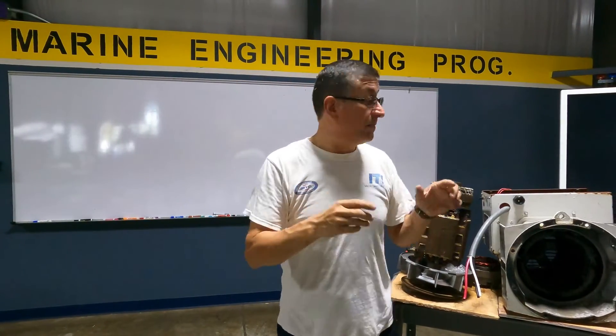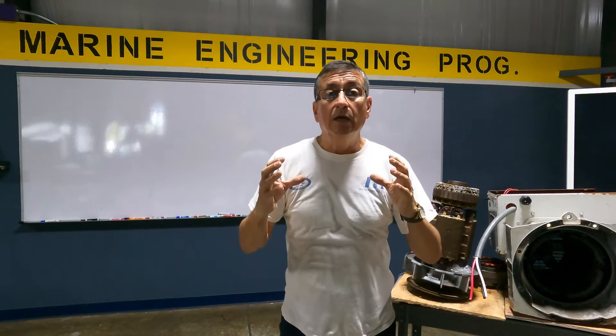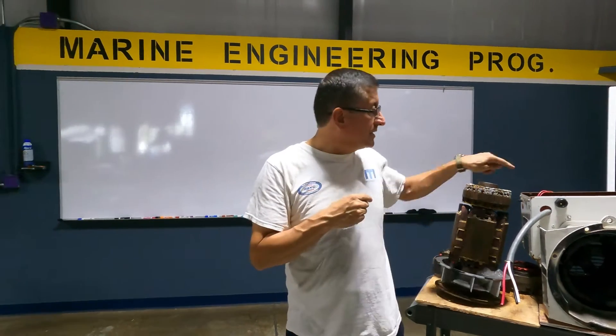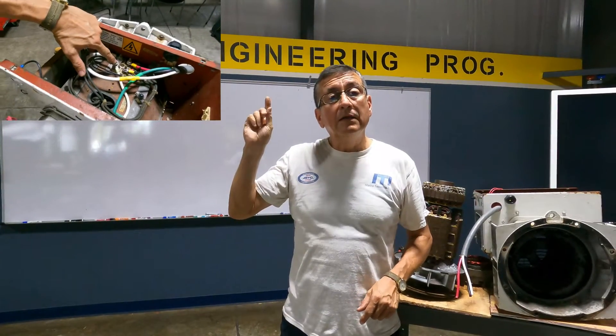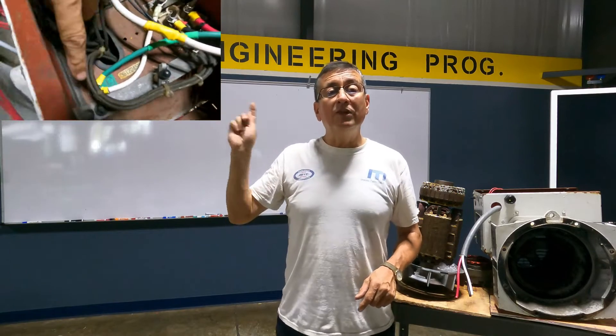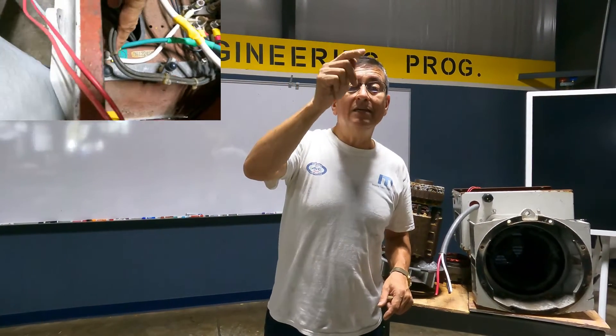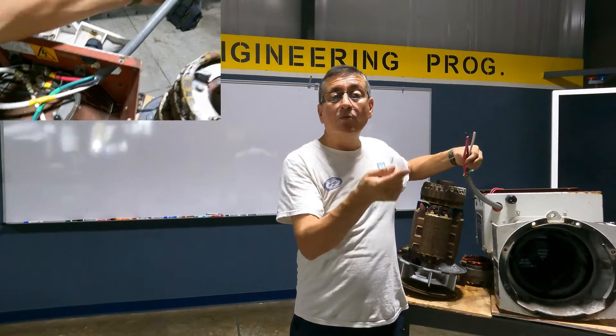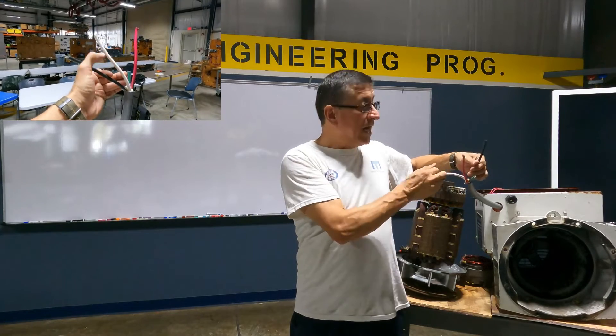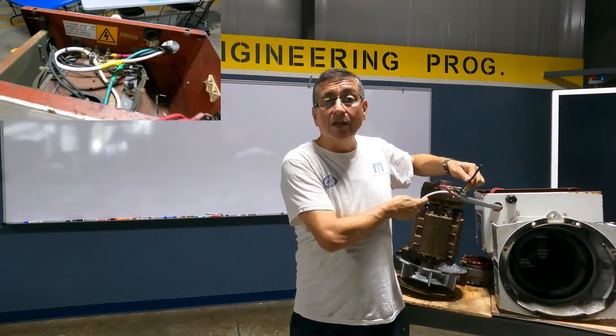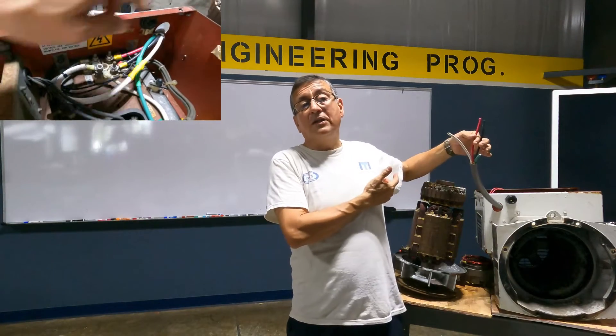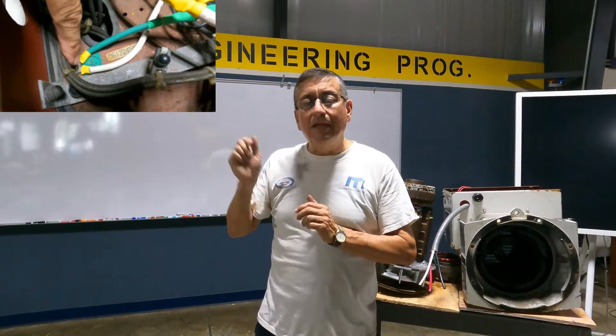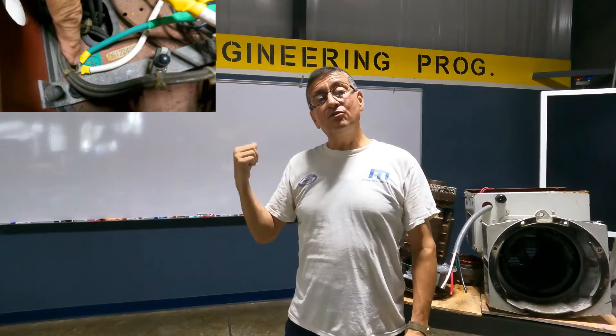At the generator, at the back end of the generator, at the transformer, or on the computer of the inverter, the neutral and the ground are together at that point. Check this on the generator: you have the neutral bus bar, and the neutral bus bar is connected with the ground point. From the neutral bus bar, a white cable enters the AC panel as neutral, and a green cable for the ground enters the ground bus bar in the AC panel. The neutral enters as the neutral bus bar. Those red and black — hot and hot — are two hot lines for phase one and phase two. In this particular case, this is a double phase generator. The neutral and the ground are connected together at that point — this is considered the source of power.